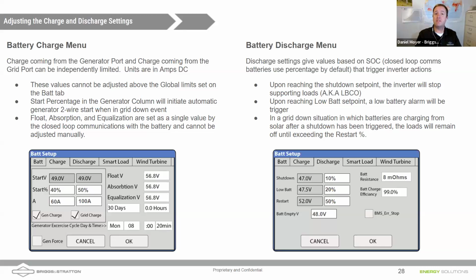So the inverter is going to stay on, but the loads will stop being supported. We then have a restart percent. What that means is that if the generator, which already should be on, or the solar comes back, or grid will recharge the batteries up to 50%, that's when the inverter will start to turn back on loads.